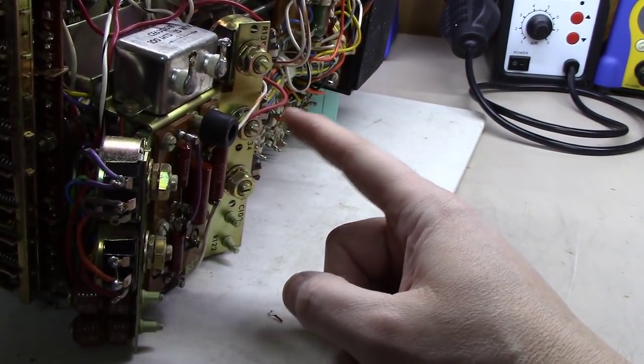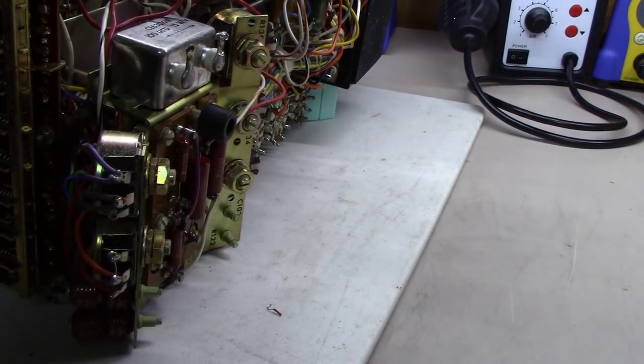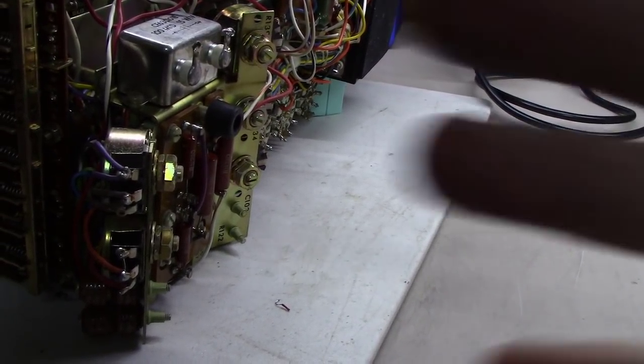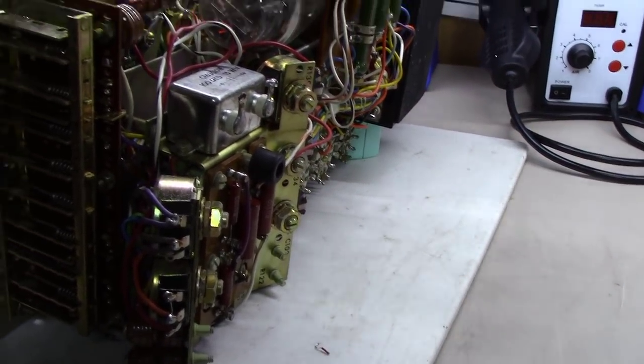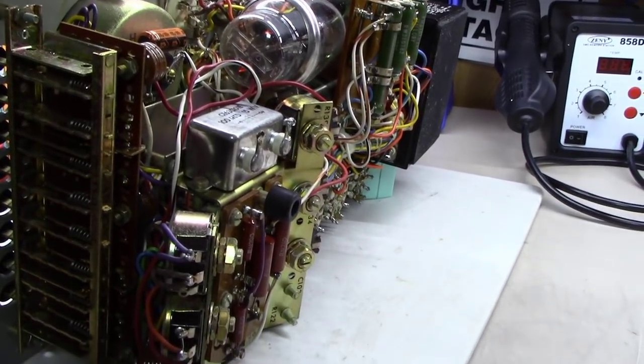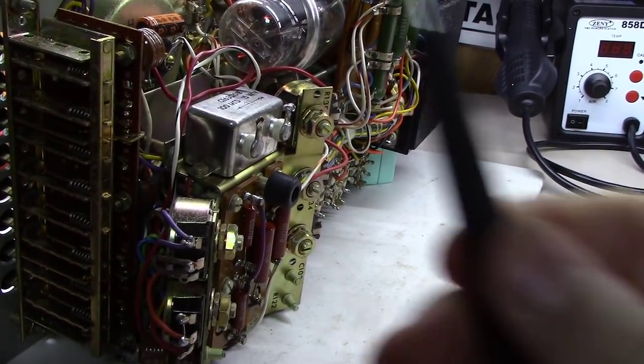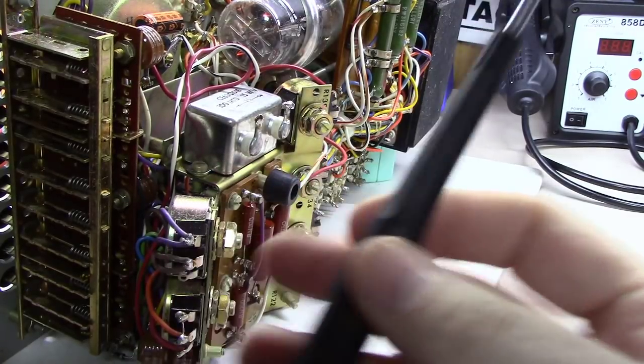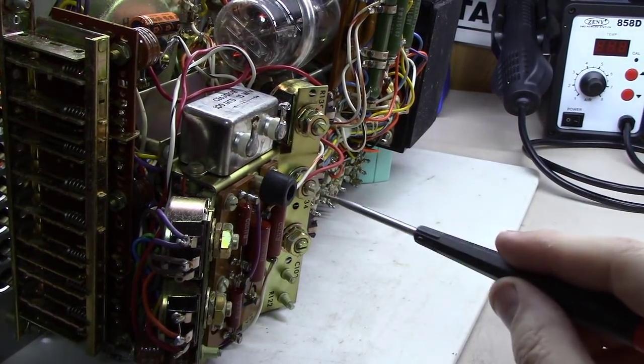So you're going to want to make sure you unlock the lock nut on the outside of it first. And keep in mind, there are high voltages flowing through this whole back side of this thing at this point. So you're going to want to be very careful. Use a screwdriver that has a good plastic handle of some sort that would insulate you.